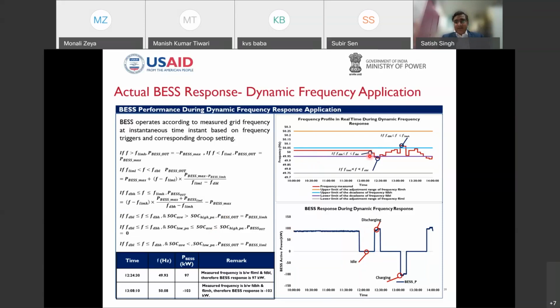And again, if there is a variation like this one, so if it is between the range, it is idle, because at this point, after some time, the SOC must have been brought back into the bands, and then it is becoming idle. Then this is discharging mode. This is because my frequency has gone below the lower band limit. And again, if this is between the range, this is fine. This is again charging mode. So battery is performing in real time. There is no time lag as such. It is responding to the observed frequency from the grid. And then we can set all these limits, slope, parameters, how much charging, discharging you want. So all those limits can be set into the control algorithm.